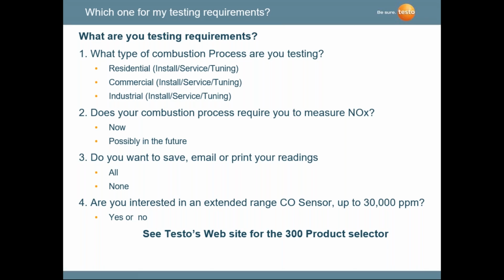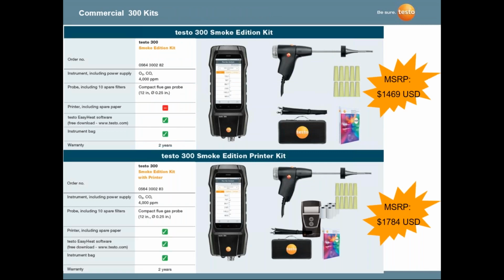This is a product selection guide that's actually on our internet site. So let's say if you're measuring oxygen and CO, and you don't want to measure NOx, these are the two models you're looking at. It's called a smoke edition. It has capability of measuring O2, measuring carbon monoxide, measuring pressure, measuring stack temperature and ambient temperature, and calculating all the combustion parameters. It comes with software, comes with a soft case. The top model doesn't have a printer. The bottom model does have a printer, and you'll see some suggested list prices attached as well.